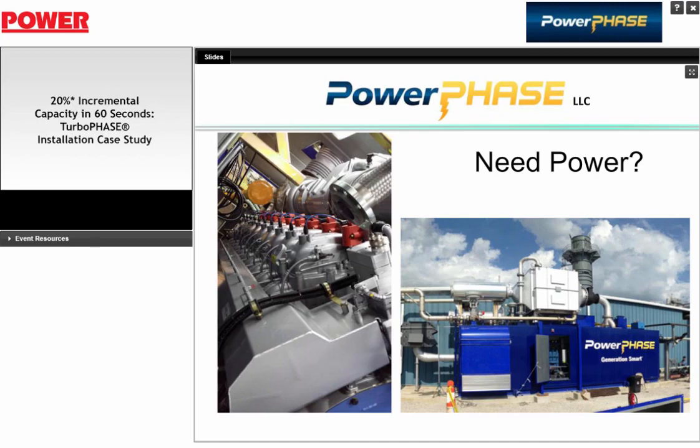Okay. What about the power consumption? What's the power consumption of both packages? So I believe it's about 35 kilowatts per module. It's on that order, and it's a 480 three-phase. We're basically talking about ventilation fans and a couple pumps that are pumping the coolant through the module. That's really all the load that's being consumed while you're running.